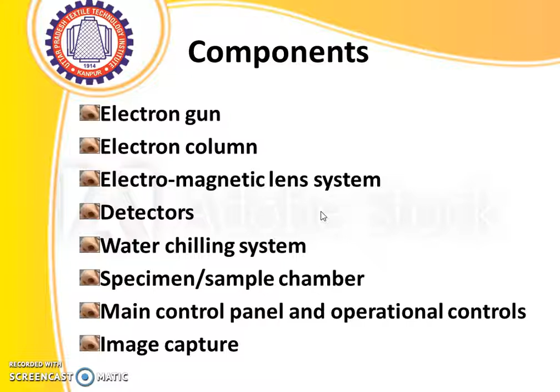The most common electron gun is the thermionic gun, in which a tungsten filament is used, or a LaB6 filament is also used, and the temperature of the electron gun goes up to about 2700 degrees centigrade. With such a high temperature, vacuum is required to keep the filament intact. The required electron energy is decided by the nature of the specimen and the type of information desired.